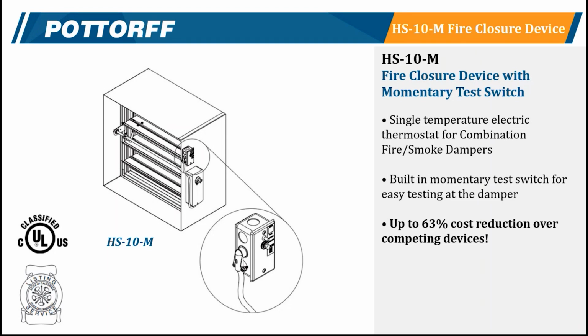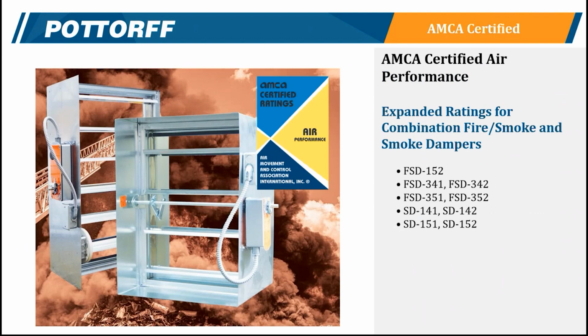This is a great option to compete against some lower costs. So if you just see a momentary switch in the specification and you don't see position indication tying back to the BMS, this is a great way to allow that, to be able to cut power to the damper and cycle it in the field.